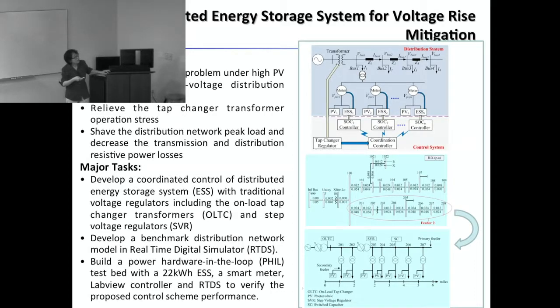Basically, if we have large penetration of PV, that will affect the voltage. So in that way, we apply distributed energy storage to work with PV together, so we can control those energy storage units first to regulate the voltage before using traditional voltage regulation devices, like tap changing transformers and SVC.